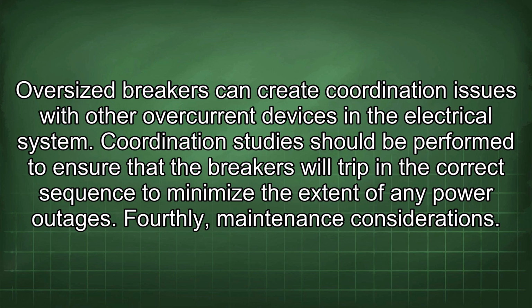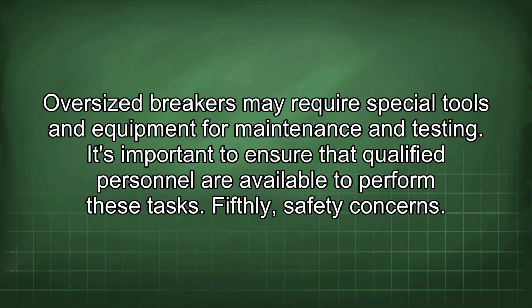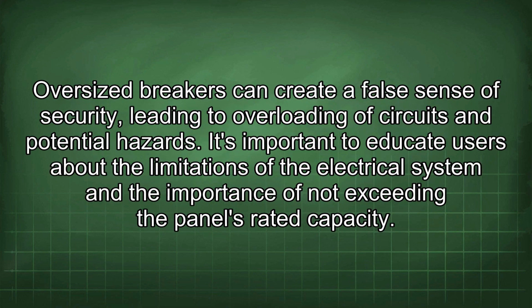of any power outages. Fourthly, maintenance considerations. Oversized breakers may require special tools and equipment for maintenance and testing. It's important to ensure that qualified personnel are available to perform these tasks. Fifthly, safety concerns. Oversized breakers can create a false sense of security, leading to overloading of circuits and potential hazards.